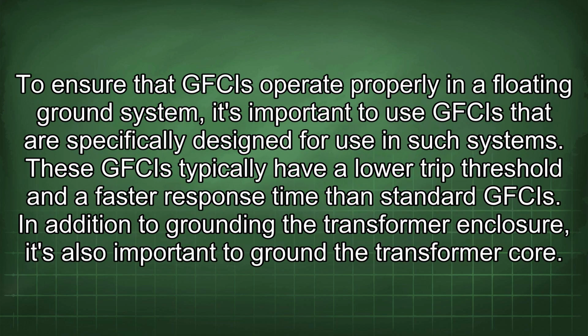To ensure that GFCIs operate properly in a floating ground system, it's important to use GFCIs that are specifically designed for use in such systems. These GFCIs typically have a lower trip threshold and a faster response time than standard GFCIs. In addition to grounding the transformer enclosure, it's also important to ground the transformer core.